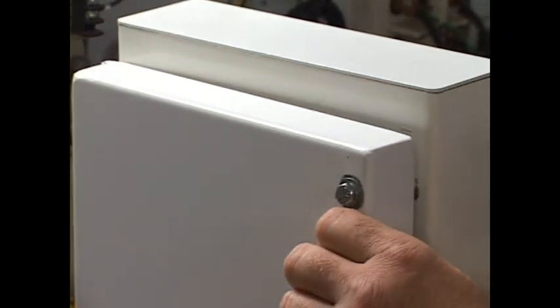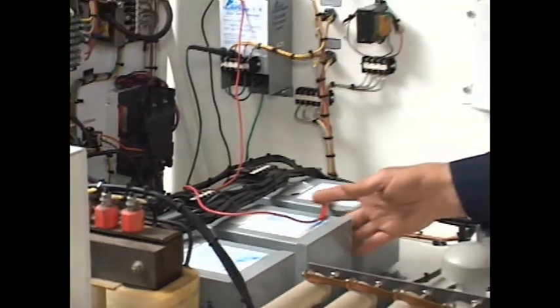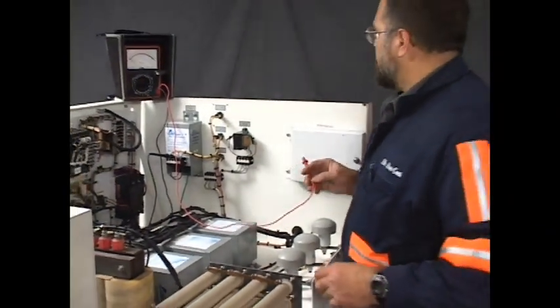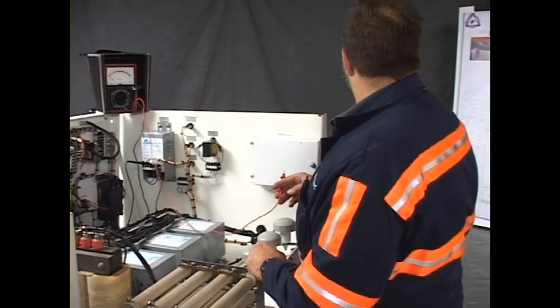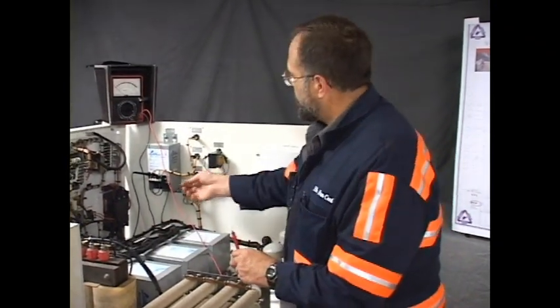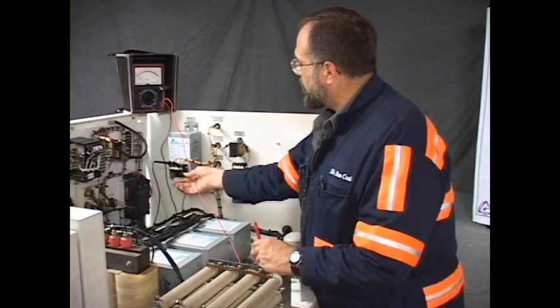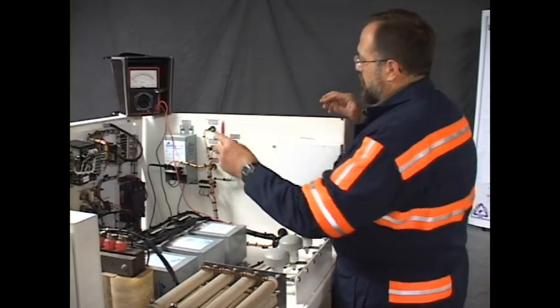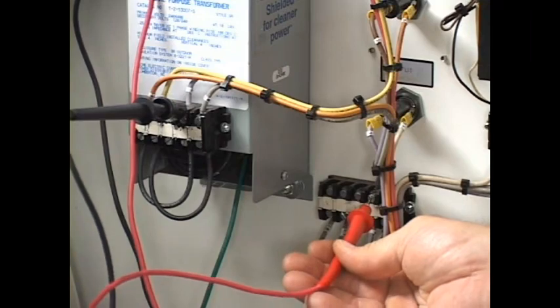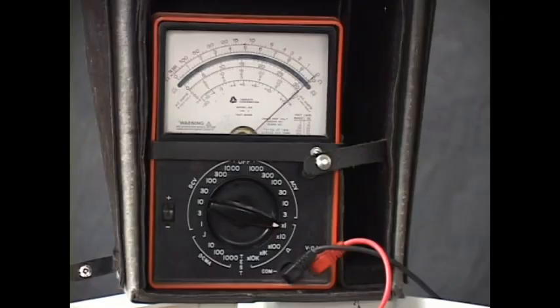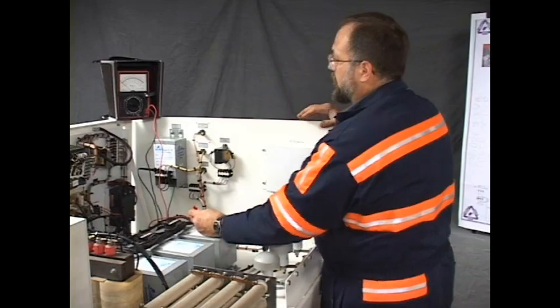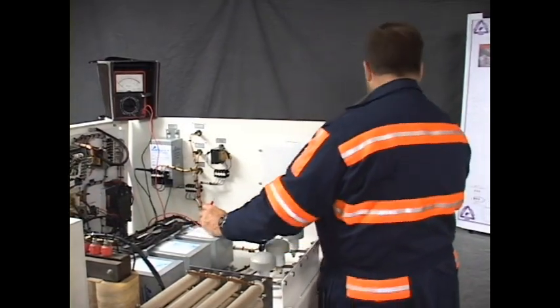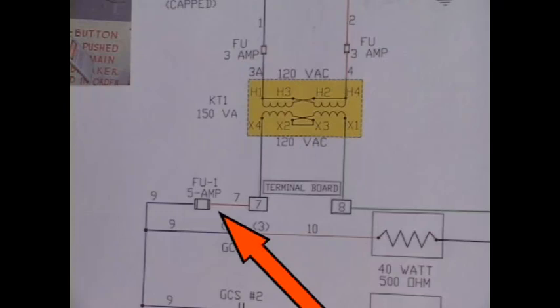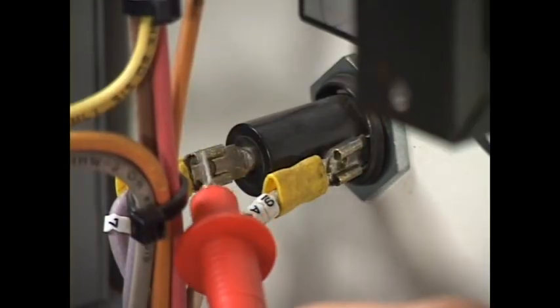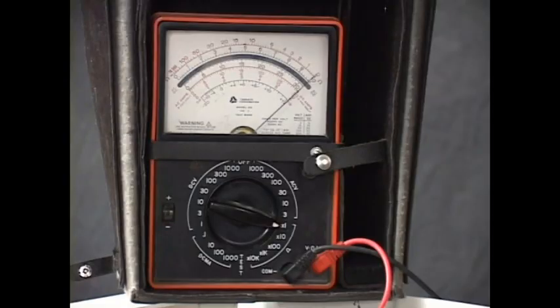The second switch, 52. And beginning as I did before, the secondary of KT1, X4 terminal, wire 7. First place it goes is to the terminal board listed on the print. There we have it. It's a good circuit, no resistance. The next point, as is indicated, from the terminal board is to the line side of FU1, wire 7. And there you have it, a good circuit, no resistance.